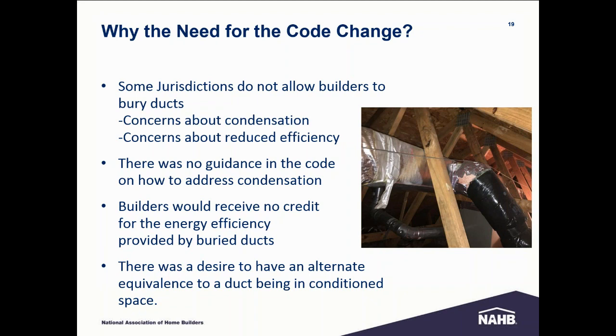And it's just, when you think about it from a building science perspective, from an energy efficiency perspective, you are taking, in the wintertime or the summertime, the coldest air in the entire house, and you're putting it into the absolute hottest place in the entire house, even the hottest part of the hottest place in the entire house, where the temperatures can be up to 160, 170, 180 degrees, and then the temperature of the conditioned air going through the ductwork is somewhere on the order of, we'll say, 50 to 60 degrees. So a very high delta T. Why don't we lower that, put it into the attic insulation, and provide additional thermal benefit?